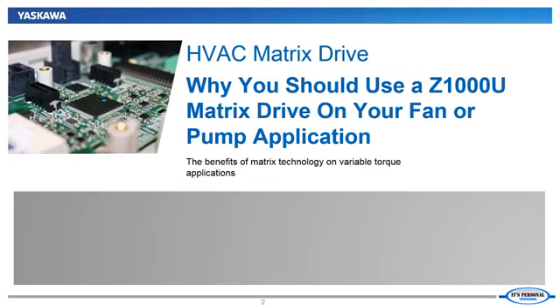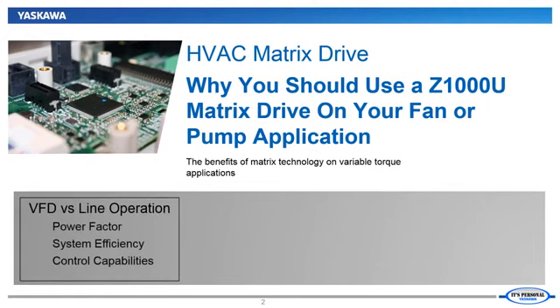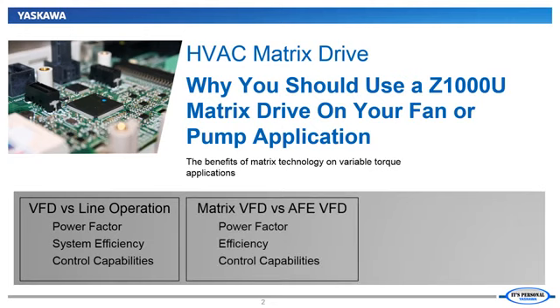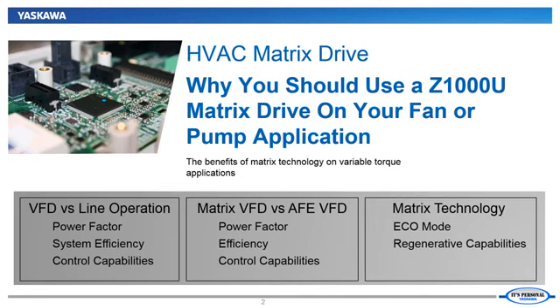In this video, we will consider the financial and functional benefits of using a Z1000U Matrix drive on a fan or pump application. First, we will establish the advantages of using any standard variable frequency drive over running a fan or pump across the line with dampers or valves to adjust the performance of the application. Then we will compare how the Yaskawa Matrix drive compares to a standard variable frequency drive or even a VFD with an active front-end package. Finally, we will review the technology behind the Matrix drive that makes it so unique.